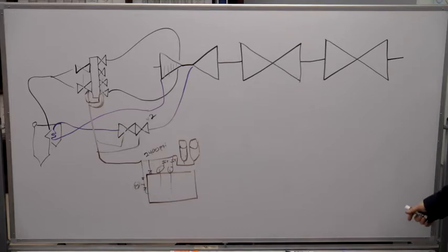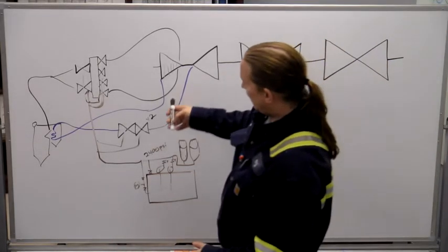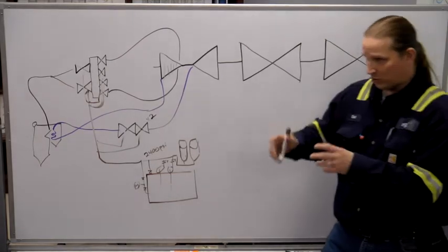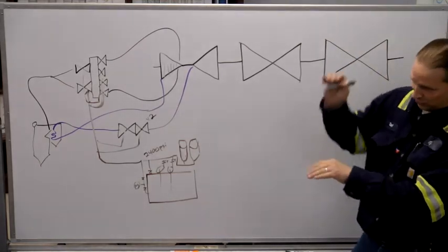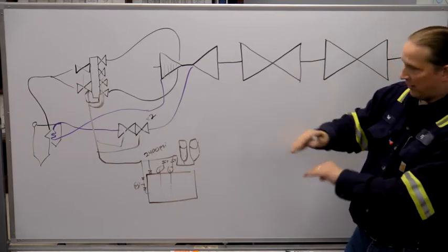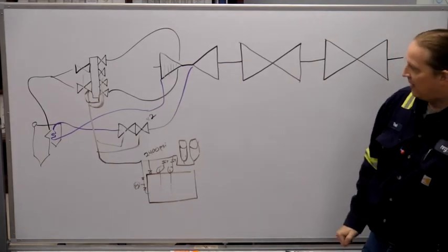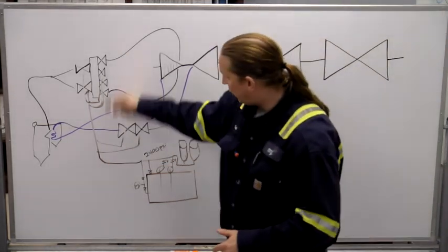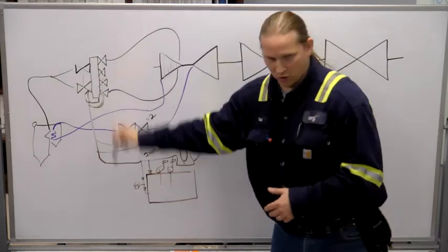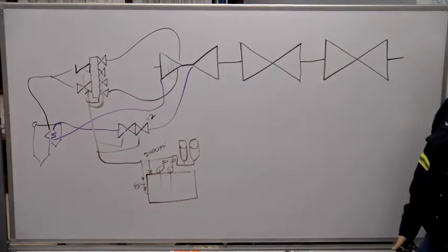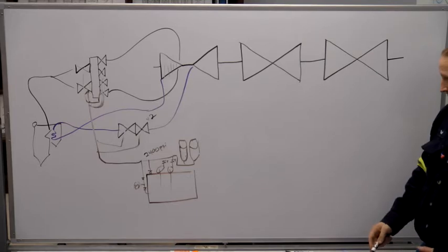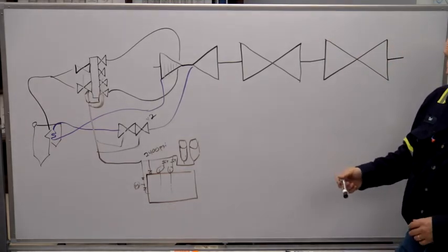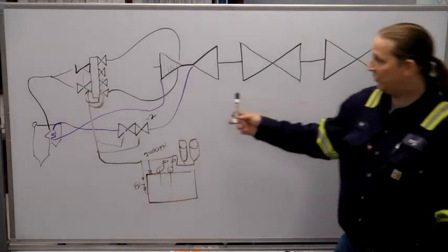If you look at the valves, there is a servo valve which controls how much oil goes on top of the piston and how much oil goes on the bottom — it's actually throttling the pressure to get it where it's supposed to be. And then there are two trip valves, either of which is able to bleed off all the oil and make all of these valves go to the shut position.